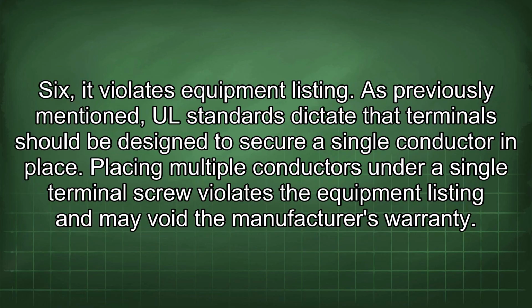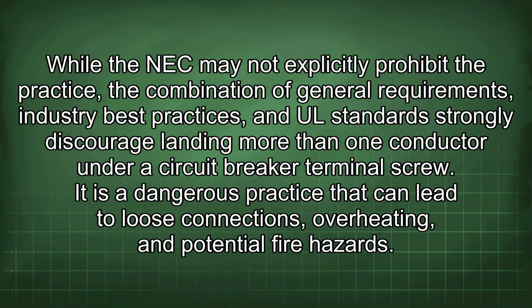6. It violates equipment listing. As previously mentioned, UL standards dictate that terminals should be designed to secure a single conductor in place. Placing multiple conductors under a single terminal screw violates the equipment listing and may void the manufacturer's warranty. While the NEC may not explicitly prohibit the practice, the combination of general requirements, industry best practices, and UL standards strongly discourage landing more than one conductor under a circuit breaker terminal screw. It is a dangerous practice that can lead to loose connections, overheating, and potential fire hazards.